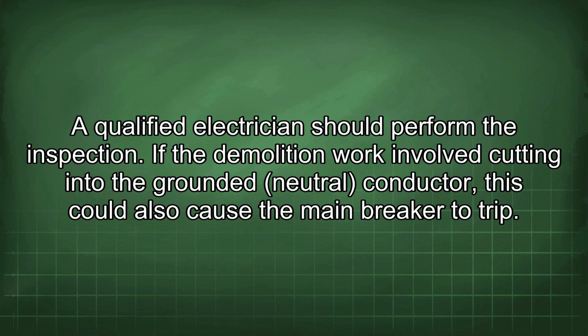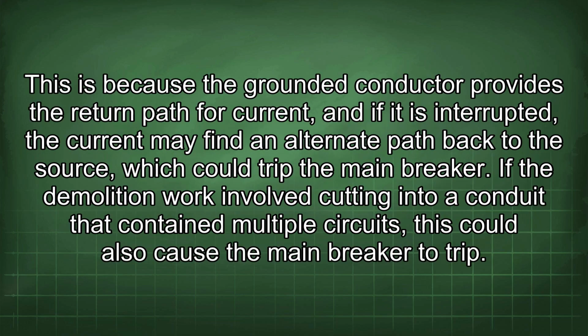If the demolition work involved cutting into the grounded neutral conductor, this could also cause the main breaker to trip. This is because the grounded conductor provides the return path for current, and if it is interrupted, the current may find an alternate path back to the source, which could trip the main breaker.